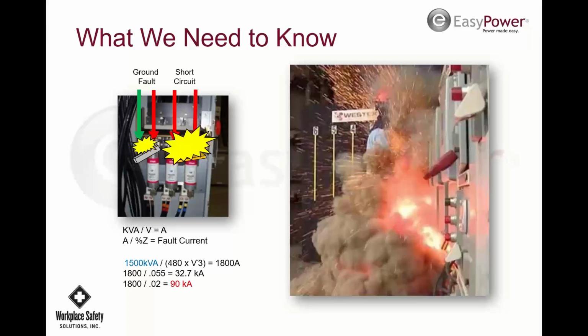Great question. So fuses are always going to be, not, I mean, you can get fast acting breakers and slow acting fuses, time delay fuses. So it all depends on the time element and the time current curve of what it is you're doing. The good thing about fuses is they don't require maintenance. Breakers require maintenance. And so if they're not maintained properly, that could delay their operation and it wouldn't be operating within the time current curve. A fuse doesn't require maintenance, so it's always going to open up the way it's supposed to according to the time current curve. So that's a good thing.